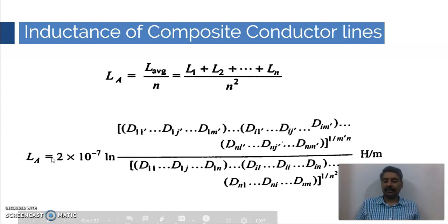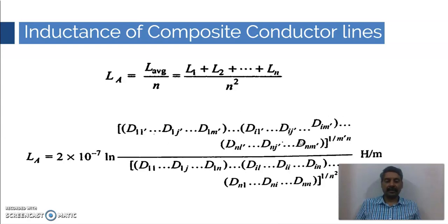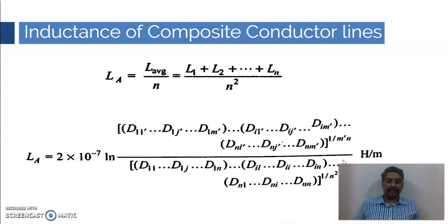It is a natural logarithm. L_A is 2 × 10⁻⁷ natural log, and we have two terms — one in the numerator and one in the denominator. We are going to give specific names for these numerators and denominators. If you see the geometrical configuration of these conductors and look at these terms, considering the numerator, it is the m′nth root of the product of all possible combinations of distances from the strands in conductor B to the strands in conductor A.